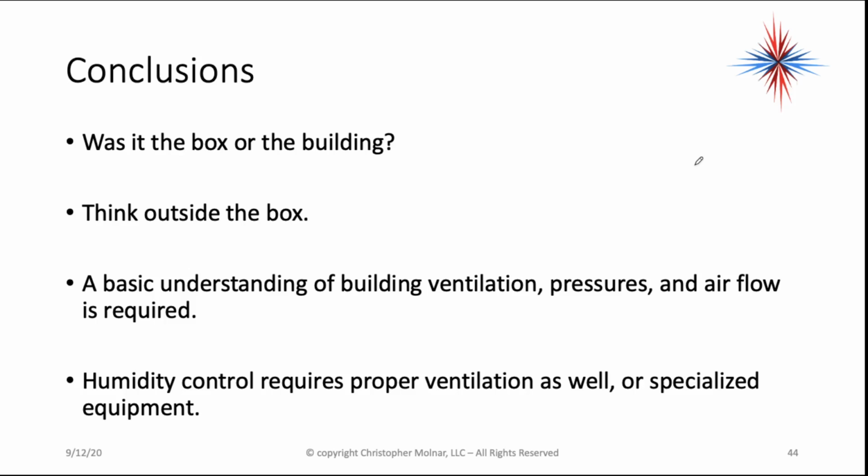So, when we go back and look at what we just went through, was it the box or the building? In this case, the air conditioning is working perfectly. It has to be the building. Think outside the box. A basic understanding of ventilation, pressures, and airflow is required. We have to remember, humidity control requires proper ventilation. We have to have proper ventilation.